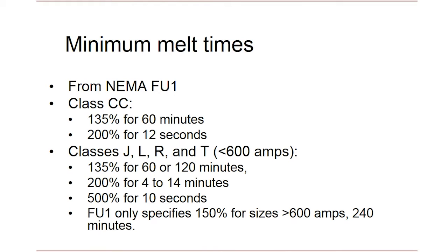For very large fuses — larger than 600 amps — the standard doesn't even define the 135% and 200% thresholds. Rather, it has a unique threshold of 150% defined for those size fuses.